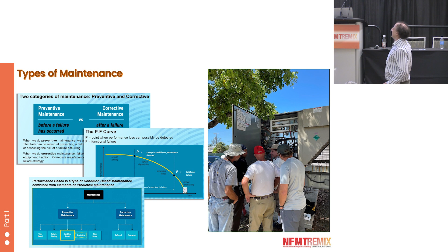This really encapsulates this slide, the PF curve—something to remember. This is the performance of the unit over time, and the yellow line drops down over time. This is what actually happens; we've taken a lot of data on package units for years and years. Point P is where you could potentially take performance readings or measurements, recognize that the performance of the unit has declined, and do something about it to get it back into a smooth running condition.